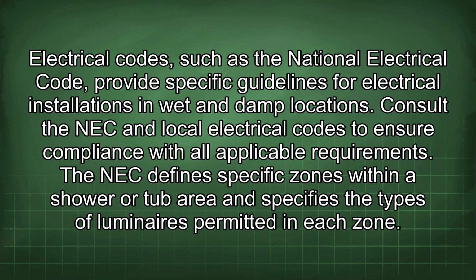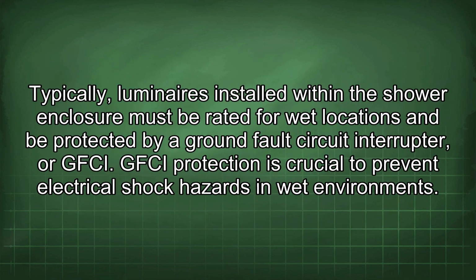Electrical codes, such as the National Electrical Code, provide specific guidelines for electrical installations in wet and damp locations. Consult the NEC and local electrical codes to ensure compliance with all applicable requirements. The NEC defines specific zones within a shower or tub area and specifies the types of luminaires permitted in each zone. Typically, luminaires installed within the shower enclosure must be rated for wet locations and be protected by a ground fault circuit interrupter, or GFCI. GFCI protection is crucial to prevent electrical shock hazards in wet environments.